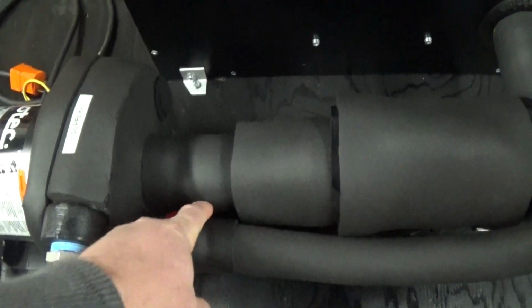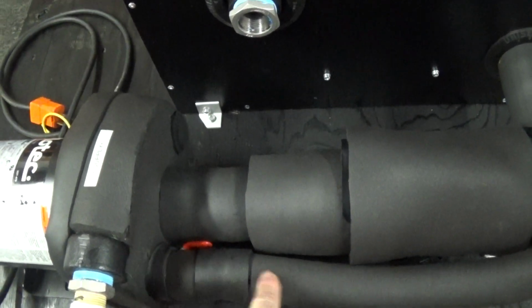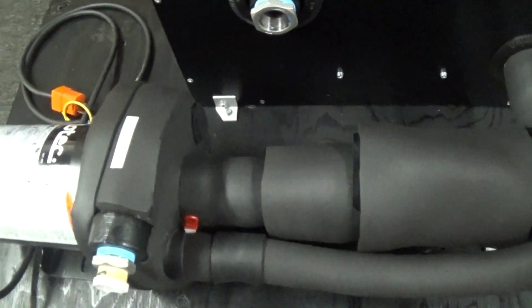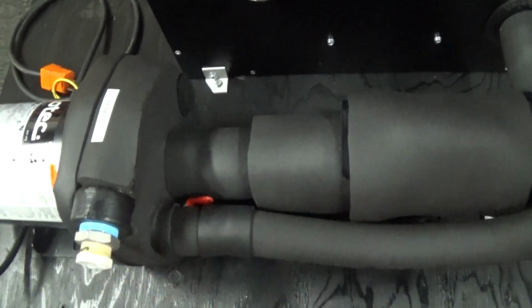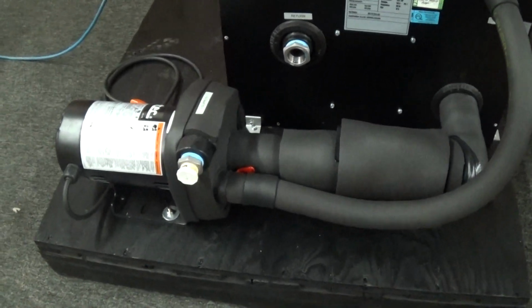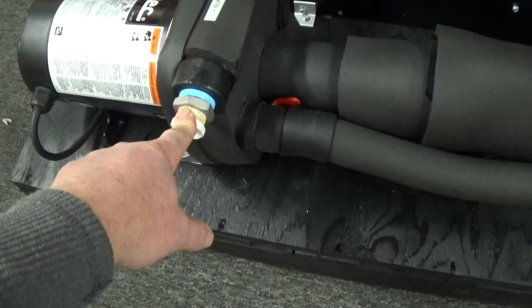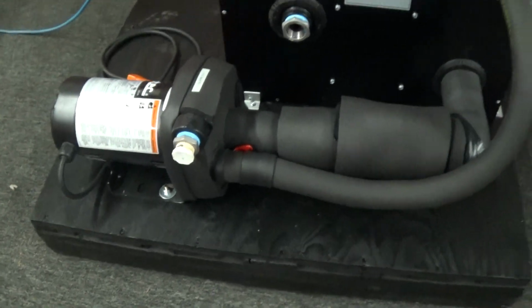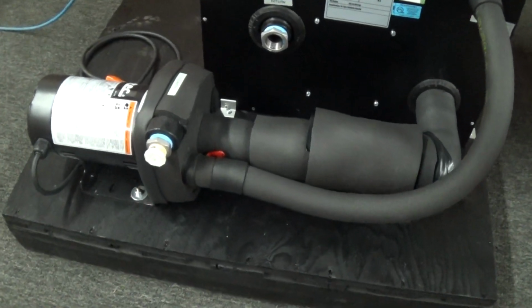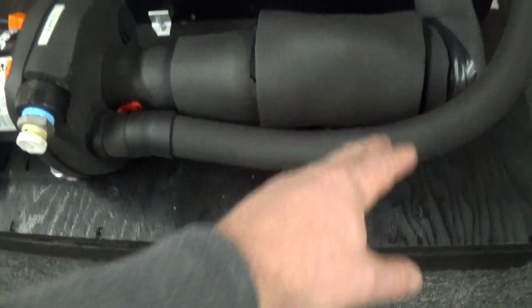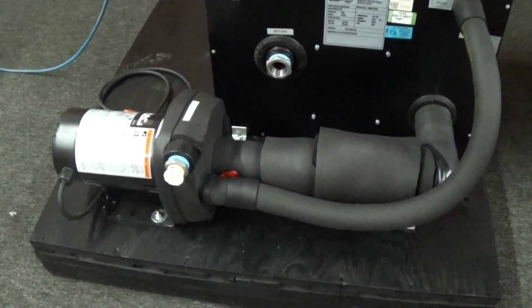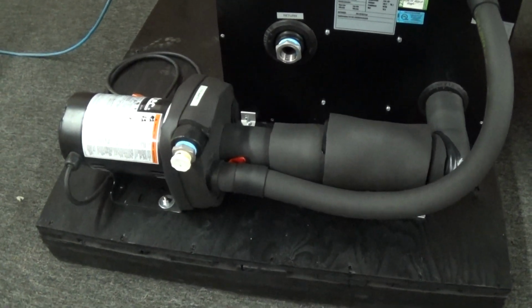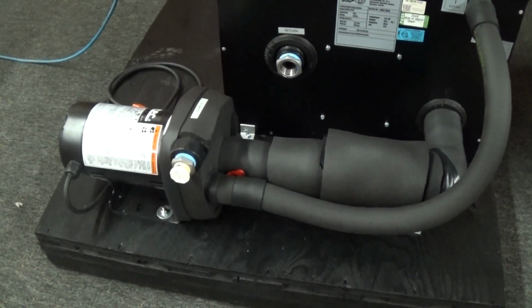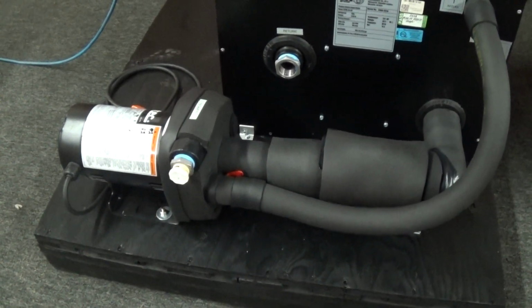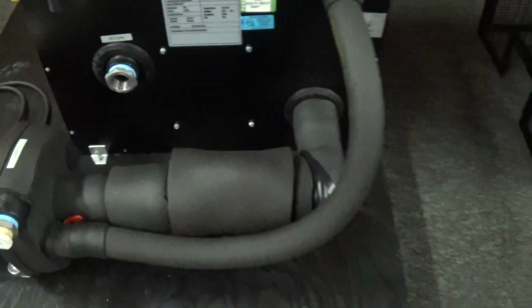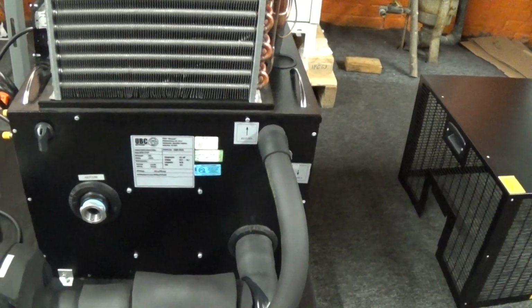You can leave this when you first start up the unit in the open position, which is parallel to the bypass line. What that is going to do is, when we're up and running, there's always going to be a certain amount of flow. And again, this is the output or supply line from the pump. There's always going to be a certain amount of flow coming back to the chiller. So when none of your fermenter tanks are calling for cooling, the chiller pump is not what they call deadheaded. We're getting some flow coming back to the Glycol reservoir here.